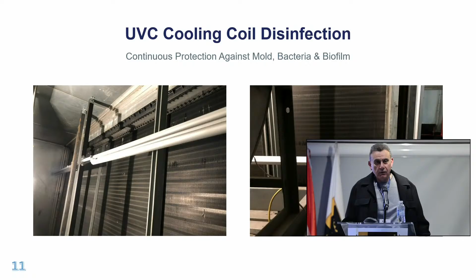Now moving along to another part of the air disinfection, which is the airstream disinfection. Now, the airstream disinfection has a bit more variables than the coil disinfection. The first and most important thing we need to understand is that the UV light bulb involved in the air disinfection needs to run parallel to the airflow, not perpendicular. It needs to be along the airflow.